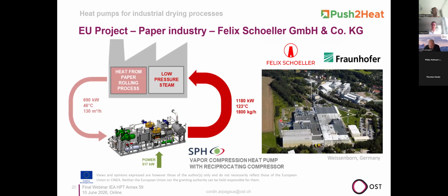Then last but not least, in my presentation, some slides about Push2Heat. This is a European funded Horizon project where we as OST are also part. And this is an installation at the paper factory in Felix Schoeller Group in Weissenborn in Germany. And what is used is a heat pump that generates steam from SPH, a German company. So they use exhaust humid air as a heat source, 46 degrees, 690 kilowatt. And then with this system, upgrade the heat again to 123 degrees to steam for the drying process.